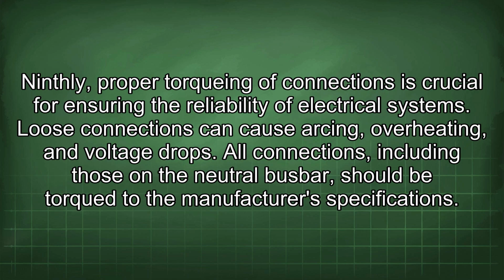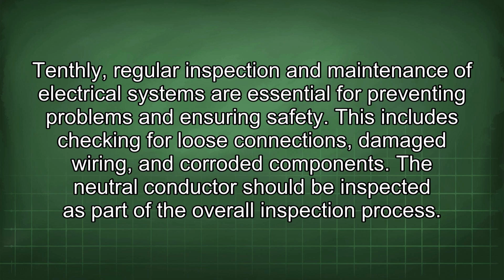Ninthly, proper torquing of connections is crucial for ensuring the reliability of electrical systems. Loose connections can cause arcing, overheating, and voltage drops. All connections, including those on the neutral busbar, should be torqued to the manufacturer's specifications. Tenthly, regular inspection and maintenance of electrical systems are essential for preventing problems and ensuring safety. This includes checking for loose connections, damaged wiring, and corroded components. The neutral conductor should be inspected as part of the overall inspection process.